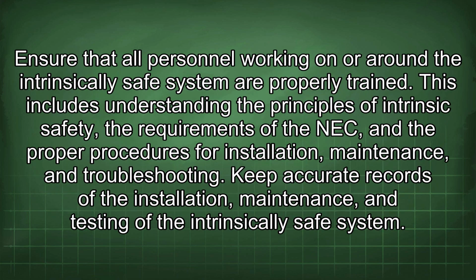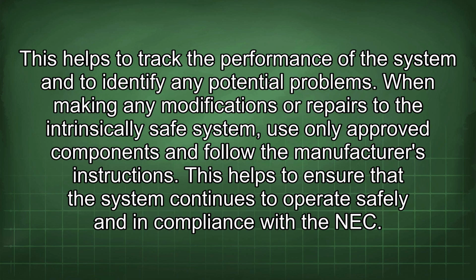Ensure that all personnel working on or around the intrinsically safe system are properly trained. This includes understanding the principles of intrinsic safety, the requirements of the NEC, and the proper procedures for installation, maintenance, and troubleshooting. Keep accurate records of the installation, maintenance, and testing of the intrinsically safe system. This helps to track the performance of the system and to identify any potential problems. When making any modifications or repairs to the intrinsically safe system, use only approved components and follow the manufacturer's instructions. This helps to ensure that the system continues to operate safely and in compliance with the NEC.